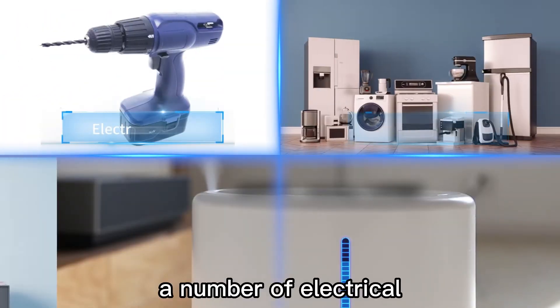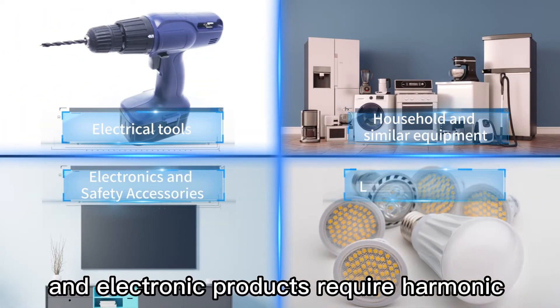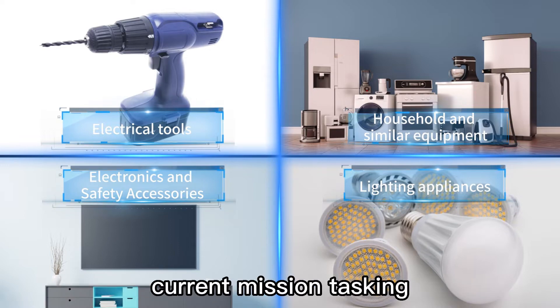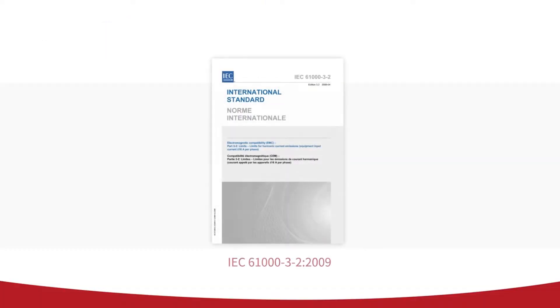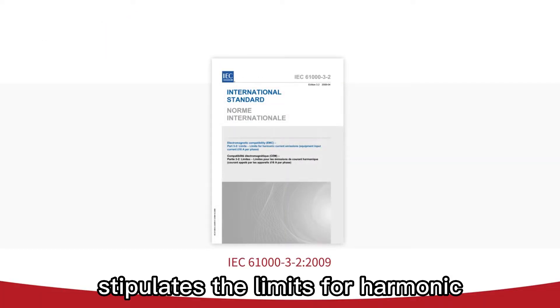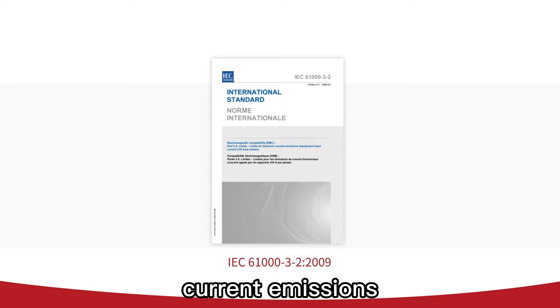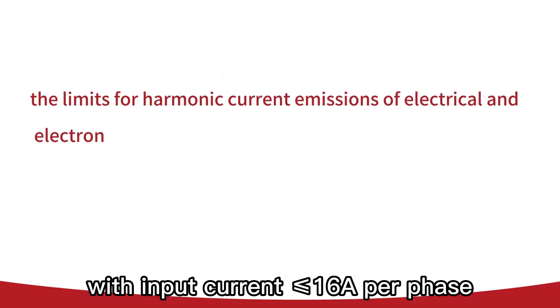A number of electrical and electronic products require harmonic current emission testing in the compulsory standards of various countries. This standard stipulates the limits for harmonic current emissions of electrical and electronic equipment with input currents less than or equal to 16 ampere per phase.